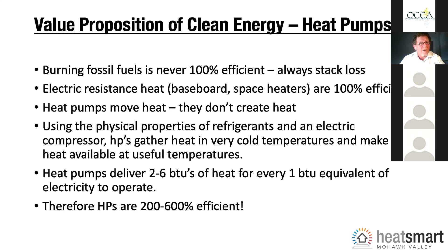And that's using a heat pump. Heat pumps operate at higher efficiencies because they don't create heat, they move heat. We use the physical properties of refrigerants and an electric-run compressor to move low-grade heat, typically from outside a building in during the heating season, or heat out of a building during the cooling season. The same system can turn right around and do both. Because we're using those physical properties of refrigerants, we can achieve efficiencies between 200 and 600% efficient. That's where the value of heat pumps is.